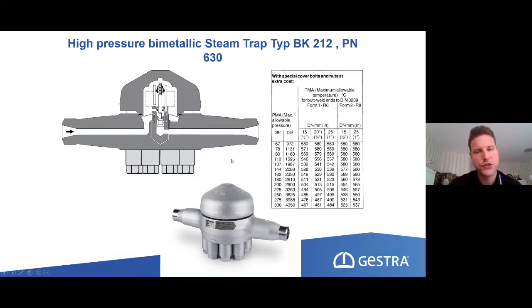So if we have, for instance, a turbine and we want to drain the turbine, we need a very good steam trap that can handle these conditions. And this is a BK212, which is able to operate at very high pressures and very high temperatures. This can go up to at least 580 degrees Celsius, and also for superheated steam. And so on, so the typical power plant application, or where we have very high pressures.